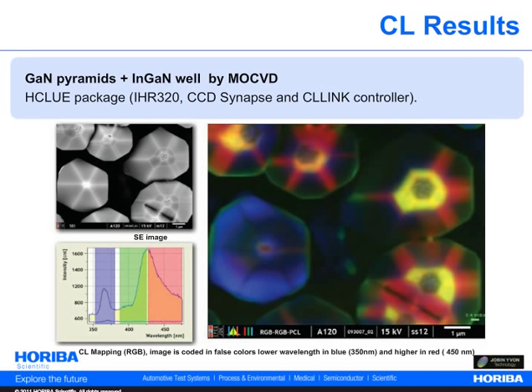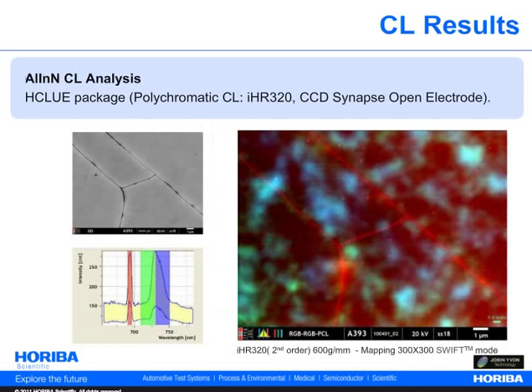The first example shows the cathodoluminescence mapping of gallium nitride pyramids and an indium gallium nitride quantum well. The image is obtained using the hyperspectral mapping capability of the HCLUE. The top left image shows the SEM image, and the image below illustrates the software capability allowing the user to select a spectral region which can then be viewed on the mapping image. For example, the blue region corresponds to the band gap of the gallium nitride.